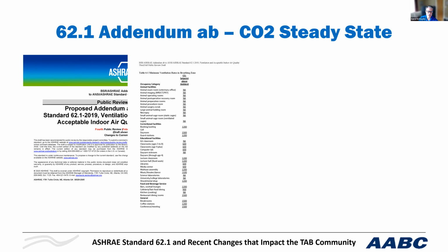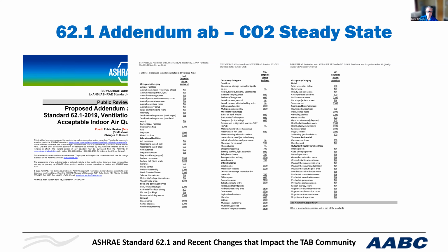So we created these tables that show all the steady state values. And these steady state values, again, are based on the area rate, the occupant rate, and the occupant load in the space. And these values are also assuming 400 parts per million. Okay, so we're showing here the differential value. So if you use a different value other than 400 parts per million, it's additive.